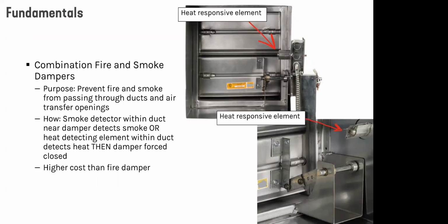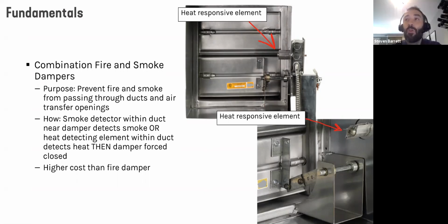Stephen, we had a question that I think would fit well in. What's the difference between a static and dynamic fire damper? Yeah, I was going to include that. So static, well, I guess we'll start with dynamic: dynamic means that the damper is able to close under flow conditions. So you should pretty much always be specifying dynamic dampers, because otherwise, if you specified a static damper, it's only going to be able to close with no airflow.